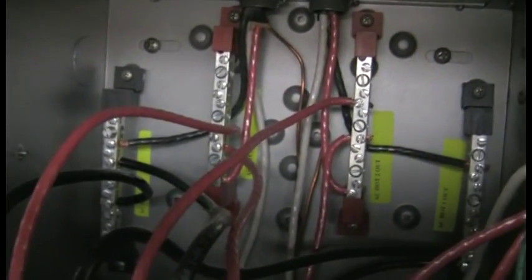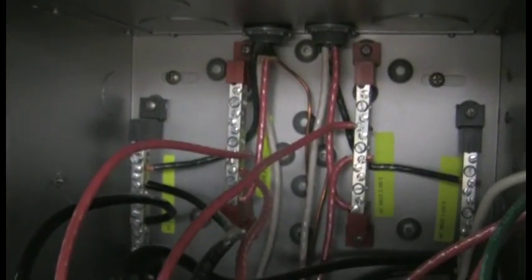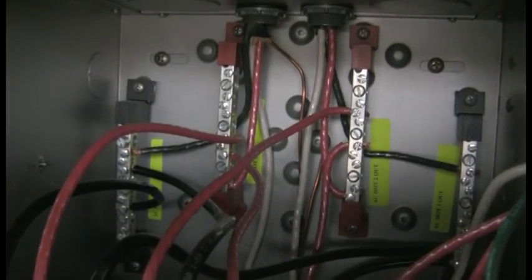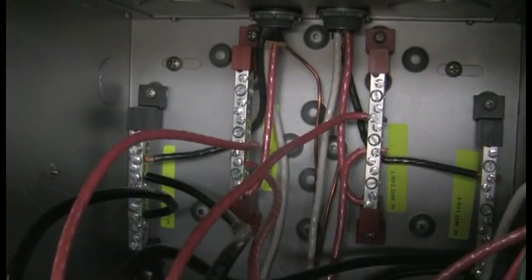When you get up here it gets interesting because you have four separate bus bars. This is designed to run in 240-volt mode, though it doesn't have to. The provisions are there if you want 240-volt mode, with AC in and AC out for both black and red terminals.